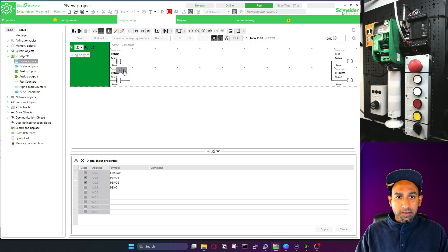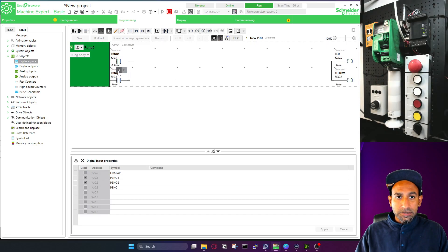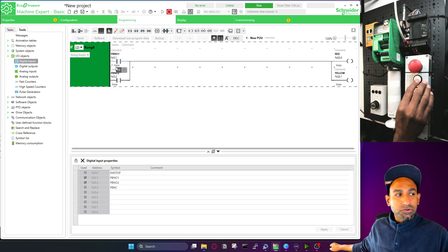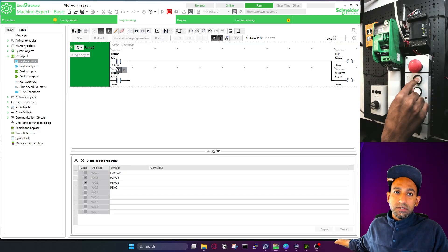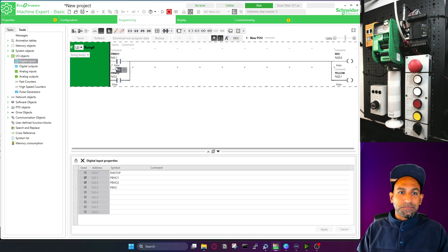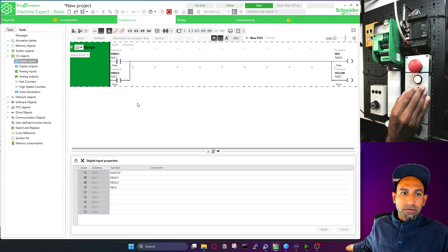I can also click force true and then force false. When I click force false, it doesn't mean the force is gone — the force is still there. When force is active and I actuate from the trainer, it will not work because I forced it to stay false. Whatever I do outside doesn't matter. I have to take out the force — now the forces are gone and there is no F here. Now I can use my input normally.